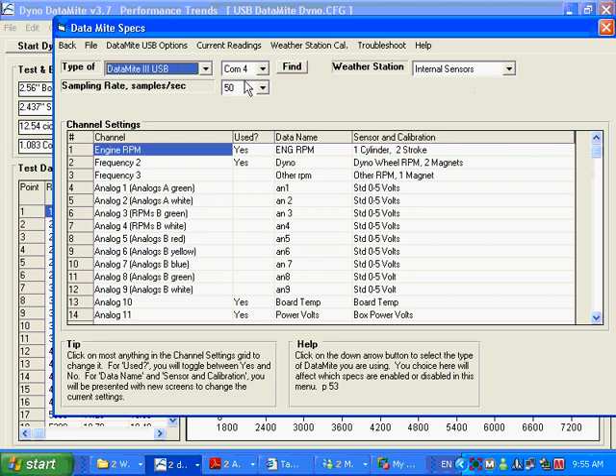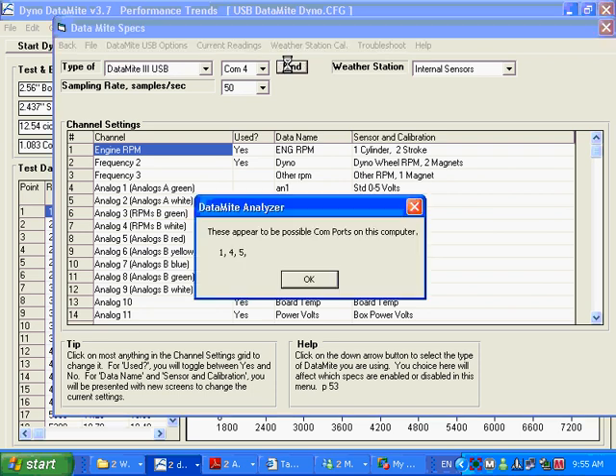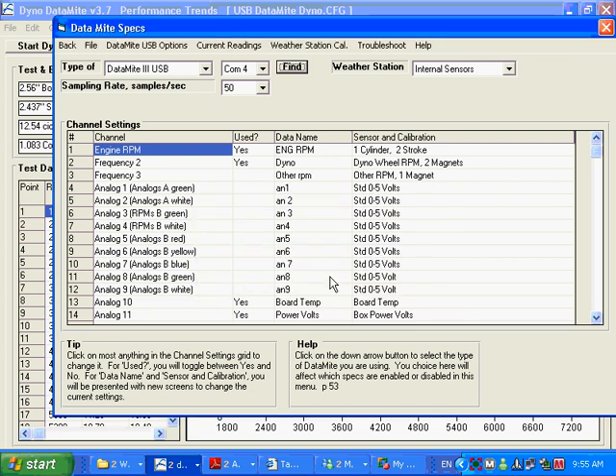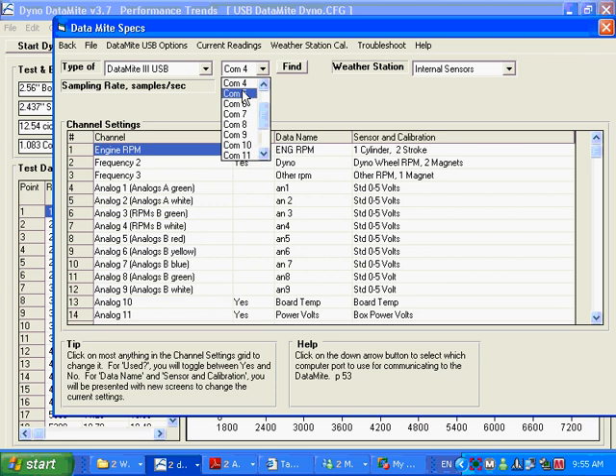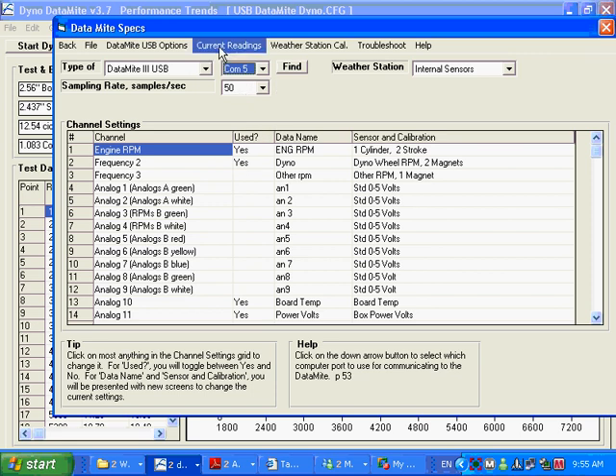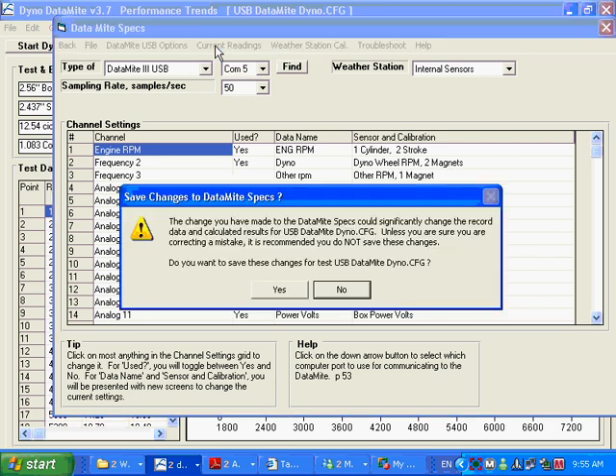What we're going to do now is we're going to see if we can find our COM port. And it says, here would be possible COM ports for this computer, 1, 4, and 5. And from my experience, typically the highest number you see here is the DataMite channel. It may not always be, but this gives you some channels to possibly check. So I'm going to change it to 5, the highest one I saw. And now let's see if we can talk to the DataMite, or at least see the readings. And that you do by clicking on Current Readings.